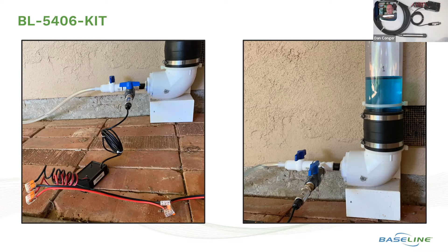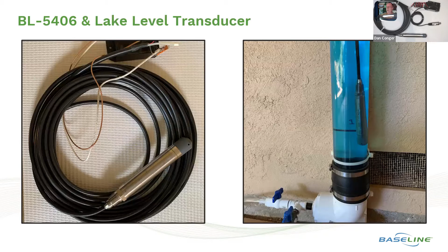This is rated from 0 to 150 psi. This lake level transducer comes with a 40-foot cord and a transducer that is rated from 0 to 5 psi, and you can buy different ones on this one. So I sought out, and it turns out this one is also a Dwyer. I bought this one, and my first impression was, wow, they're so different. And then, playing with them in my laboratory, I realized, what does this little cap do? So I pulled off this cap, and it occurred to me these two are exactly the same. There's nothing magical about this.